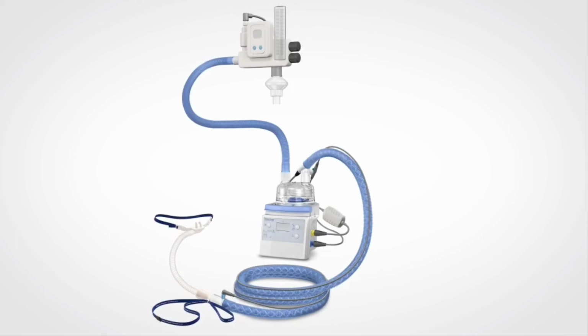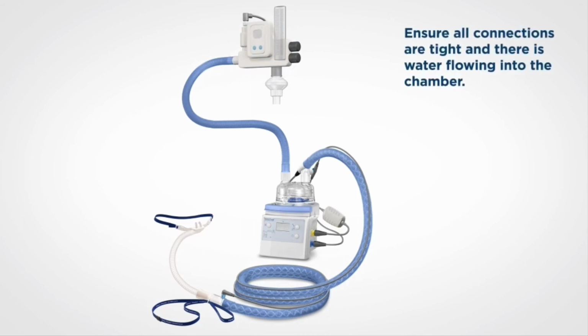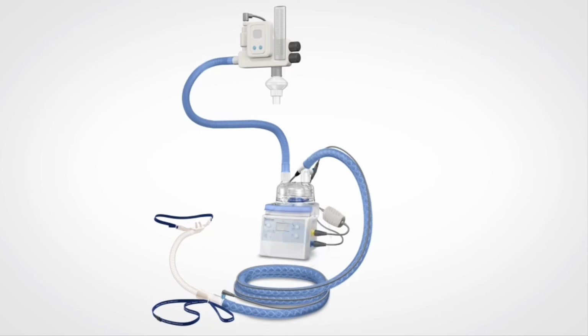In this example, we'll look at delivering blended gas through OptiFlow nasal cannula. The breathing circuit setup is identical to the inspiratory limb setup that we've previously seen. In this case, the breathing circuit is attached to an air-oxygen blender. When you're ready to use the humidifier, ensure all connections are tight, that there is water flowing into the chamber, and turn the device on by pressing the On Standby button. Optiflow should be delivered using the default invasive mode on the humidifier.